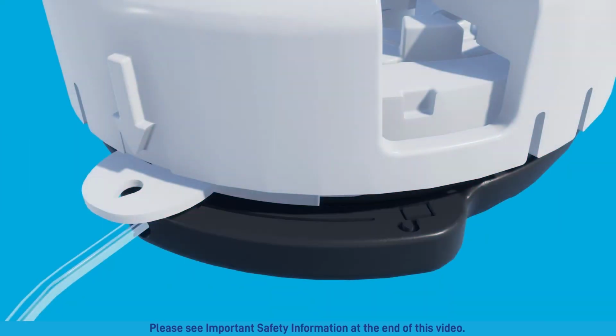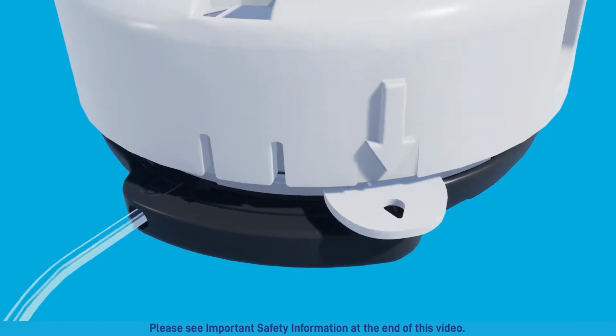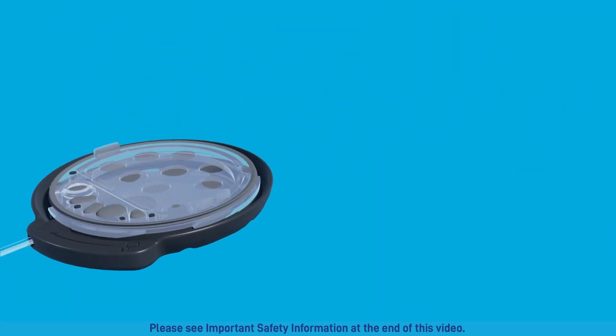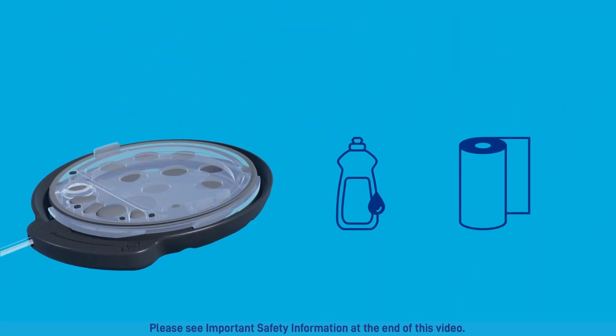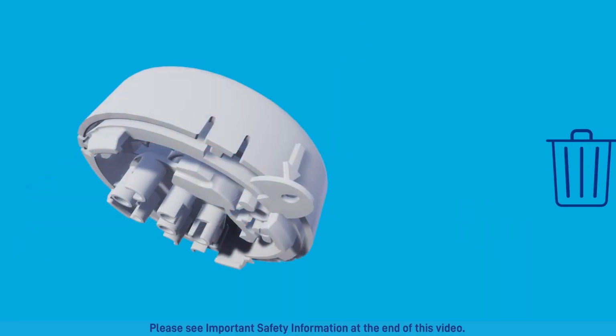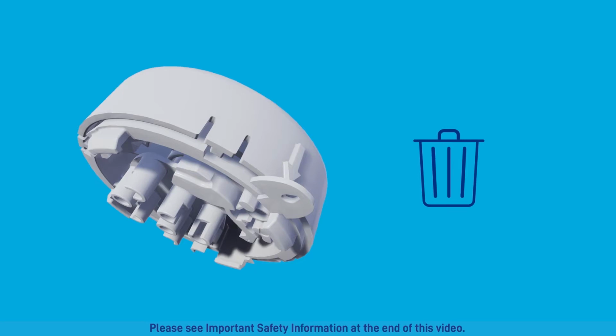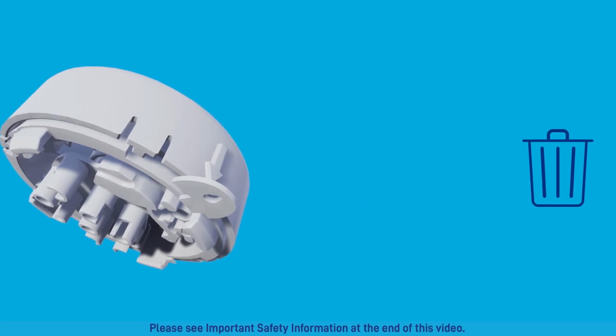When you see drops at the end of the infusion set, rotate the priming aid counterclockwise until the tab becomes aligned with the unlock symbol on the cassette. Then, detach the priming aid from the cassette. Wipe any medication from the cassette's top with an absorbent cloth or towel, and then dispose of the priming aid in your household trash. Make sure you do not dispose of the newly filled cassette. Your cassette has been primed successfully.